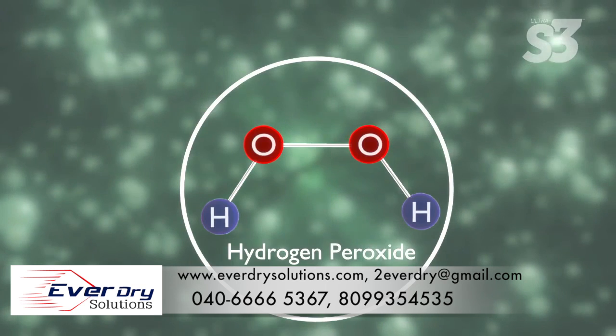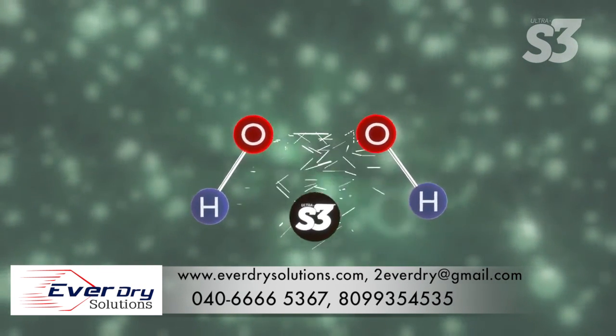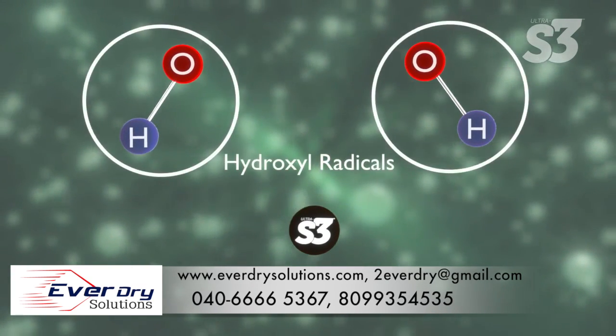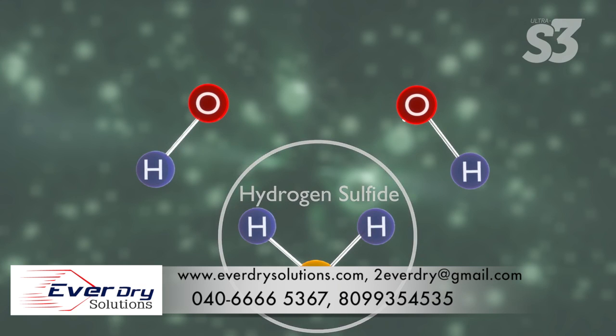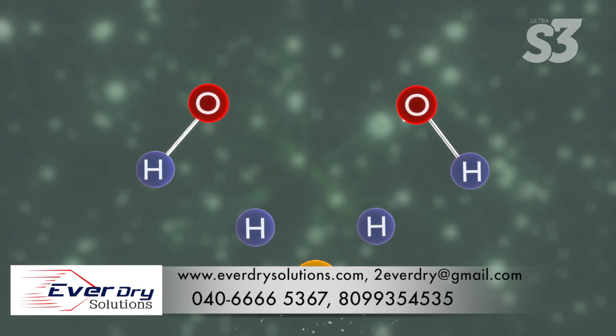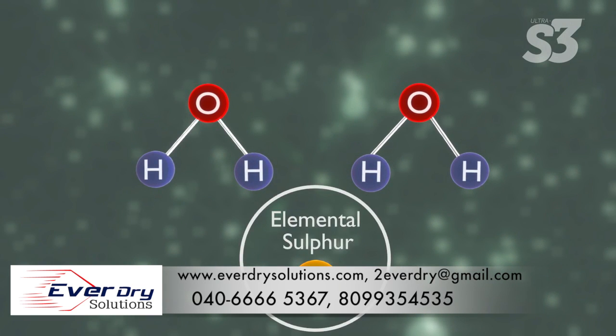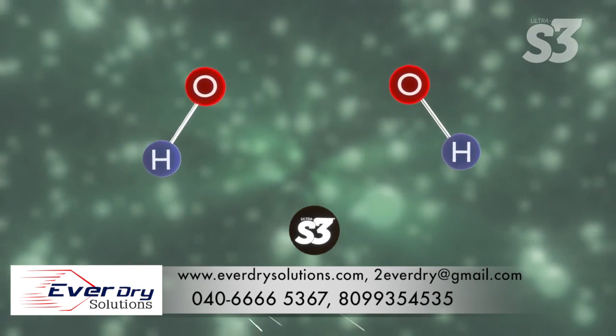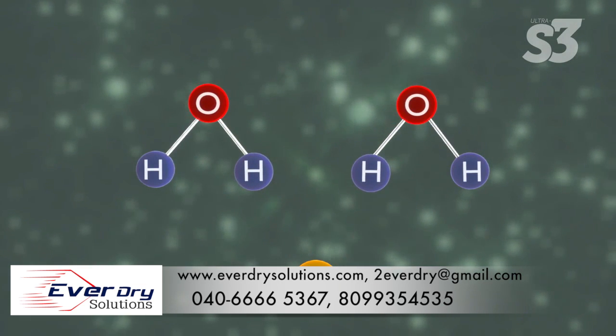In this case, hydrogen peroxide is the oxidant — it's present in the water with hydrogen sulfide and S3. S3 splits one hydrogen peroxide molecule into two hydroxyl radicals, which are much more effective at neutralizing H2S than hydrogen peroxide alone. The hydroxyl radicals neutralize the hydrogen sulfide molecule, removing the hydrogen atoms and leaving behind elemental sulfur. S3 continues to create hydroxyl radicals from hydrogen peroxide, enabling the rapid conversion of hydrogen sulfide into elemental sulfur.